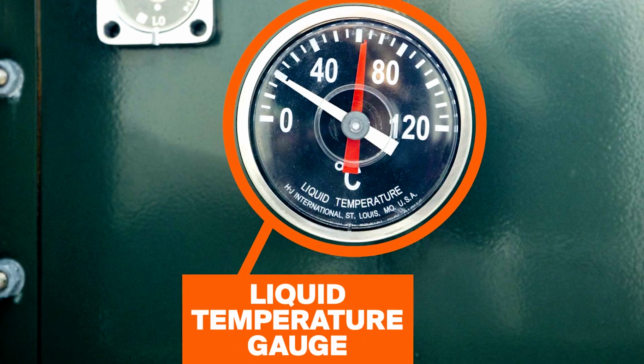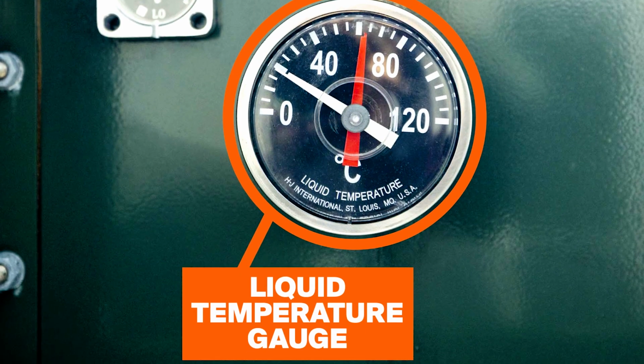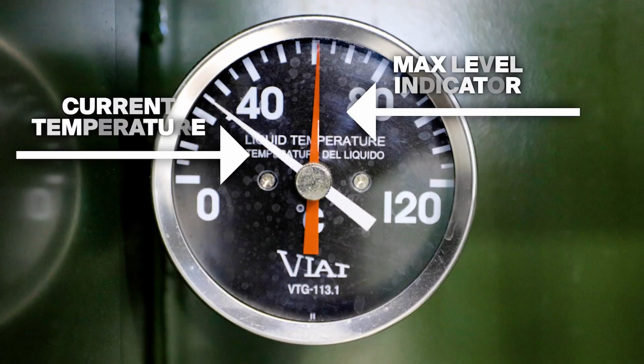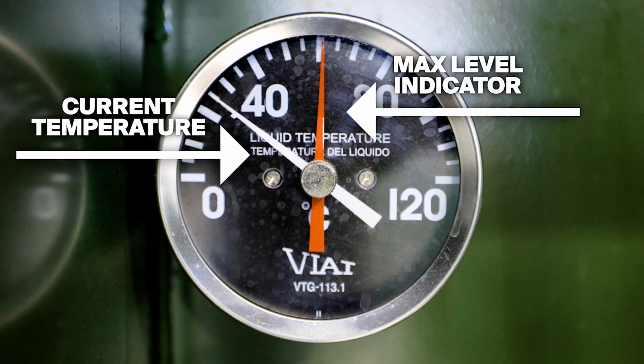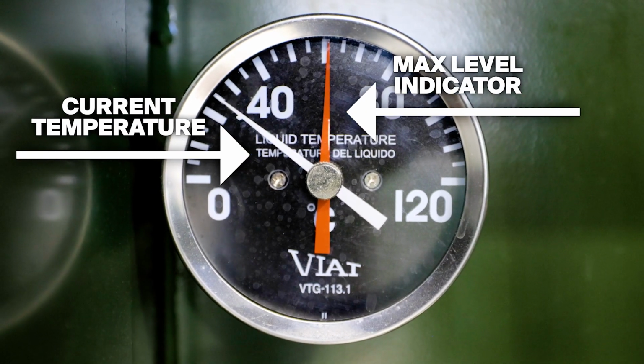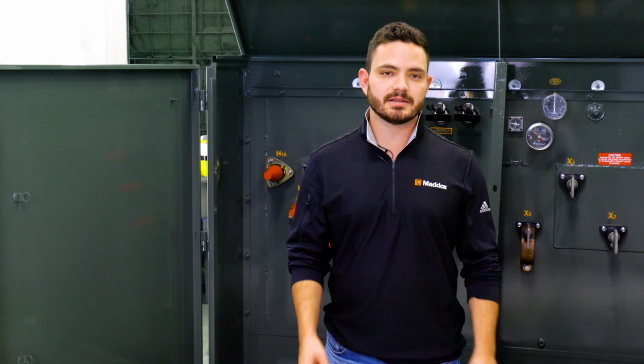The liquid temperature gauge shows the temperature of the oil inside the transformer tank. The red pointer on the temperature gauge is the maximum level indicator, which shows the highest operating temperature that the gauge has registered. Since temperature readings vary, knowing the peak temperature helps you to understand if the unit has been operated above its insulation rating.